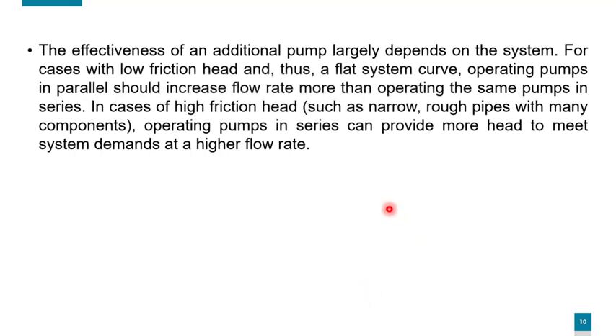The effectiveness of an additional pump largely depends on the system. For cases with low friction head and thus a flat system curve, operating pumps in parallel should increase flow rate more than operating the same pumps in series, as we've seen in the curve before in this video. In cases of high friction head, such as narrow rough pipes with many components, operating pumps in series can provide more head to meet system demands at higher flow rate.